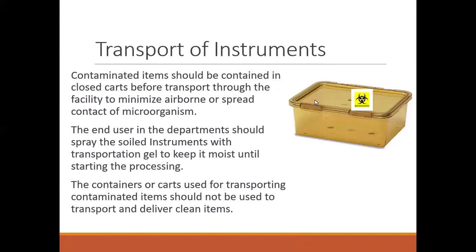Still there is time, no? Or this is very important: for transporting used instruments, which are contaminated, we have to have a closed container and there should be a biohazard sign. It should be transported to CSSD directly.